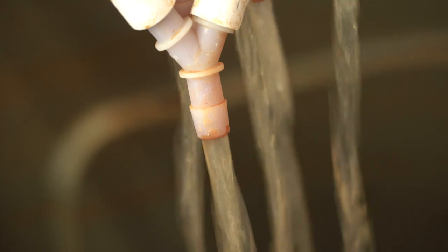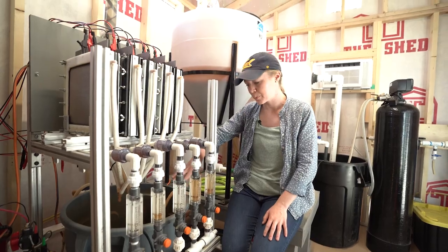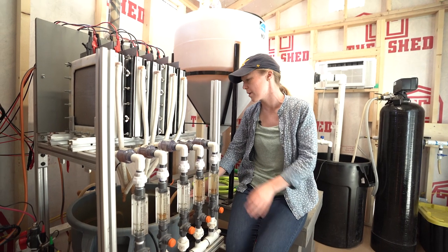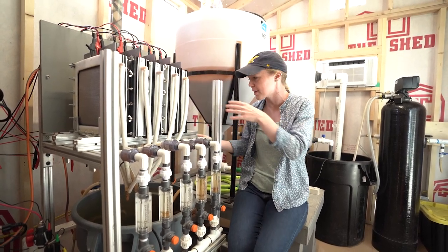The water we collect in this tank is all of the rusty water that we just created in the above electrochemical reactors. The rusty water then gets pumped out with a submersible pump and dosed with alum, a coagulant, to bring particles together and make them bigger.